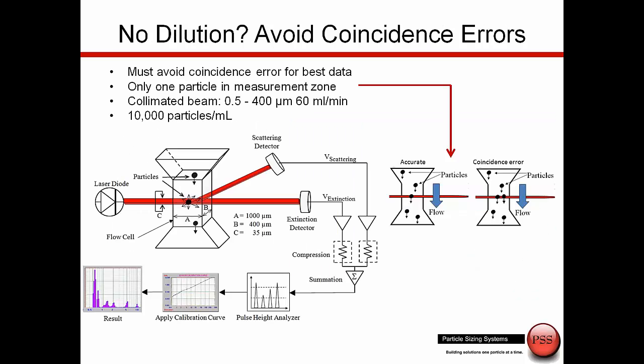So now that we've talked about why LPCs are important, let's start looking at the measurement that is required. As I talked about dilution versus non-dilution, let's talk about why this is important. This is an image of our LE400 sensor. There's a light source. There are 2 detectors.